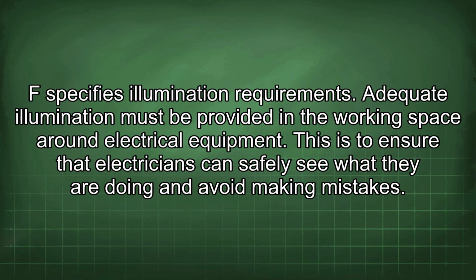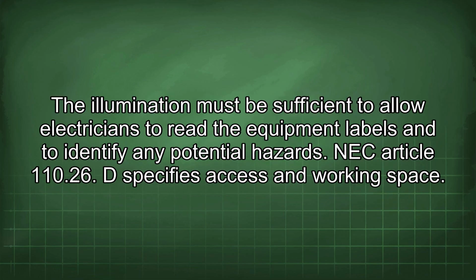NEC Article 110.26 F specifies illumination requirements. Adequate illumination must be provided in the working space around electrical equipment. This is to ensure that electricians can safely see what they are doing and avoid making mistakes. The illumination must be sufficient to allow electricians to read the equipment labels and to identify any potential hazards.